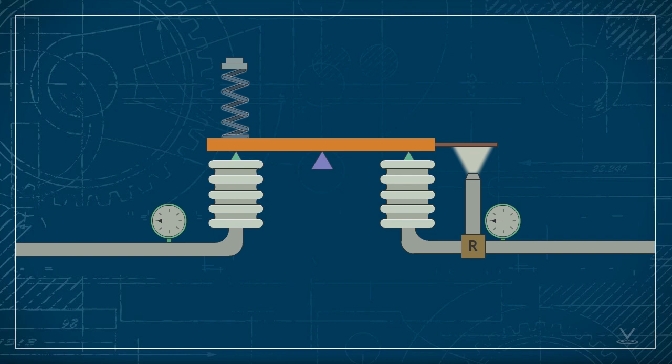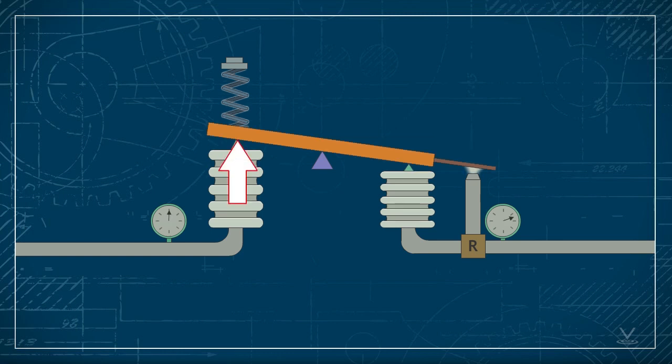Let's see how all the controller's mechanisms work together when the process variable exceeds setpoint. The input bellows expands and its force overcomes the tension of the setpoint spring. The controller is now out of balance. When the input bellows expands, the beam pivots, bringing the flapper closer to the nozzle and increasing back pressure.